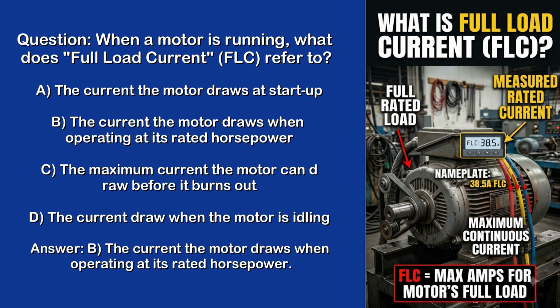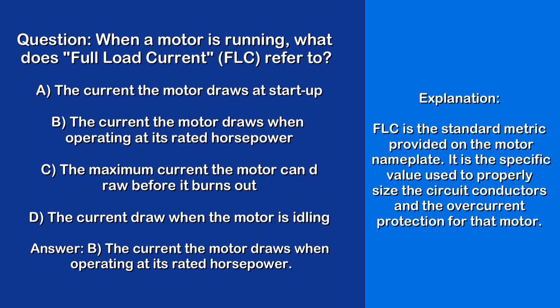Answer. B. The current the motor draws when operating at its rated horsepower. Explanation. FLC is the standard metric provided on the motor nameplate. It is the specific value used to properly size the circuit conductors and the overcurrent protection for that motor.